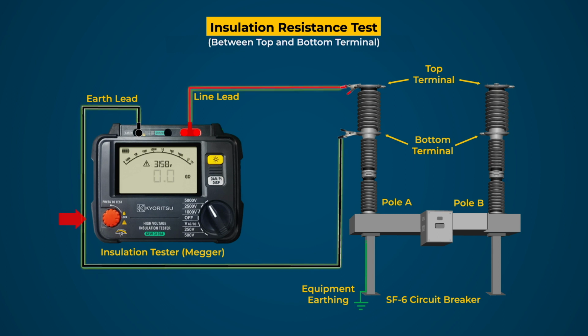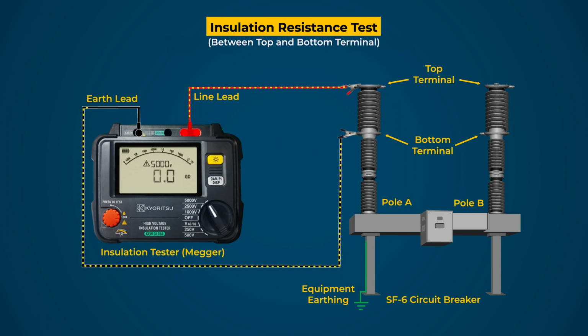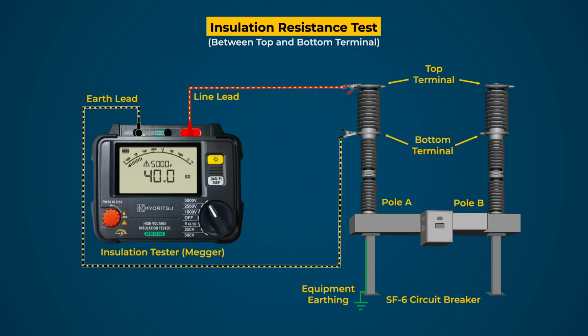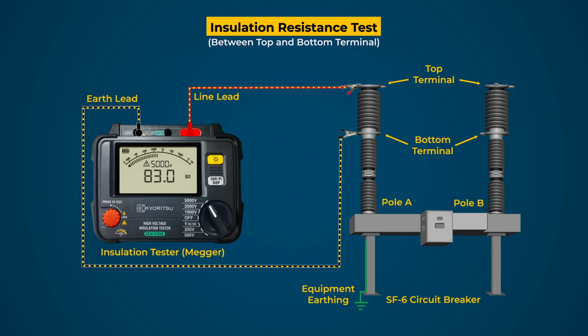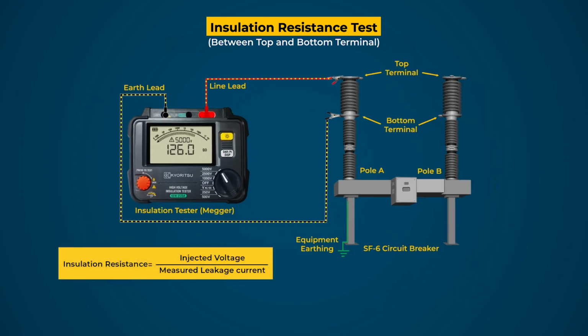By this, a DC voltage is applied across both terminals of pole A. As a result, leakage current will flow in the circuit, and the tester measures the flow of leakage current and calculates the insulation resistance value by the ratio of injected voltage and measured current. Record the displayed value of IR and compare the value with earlier records or OEM recommendations.